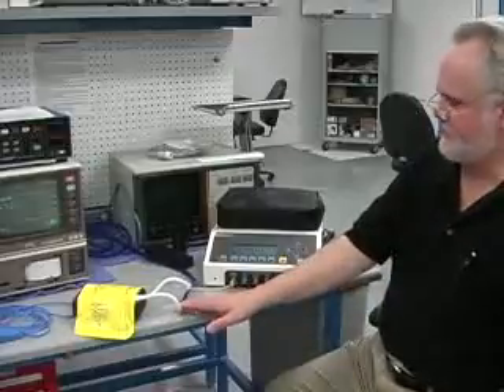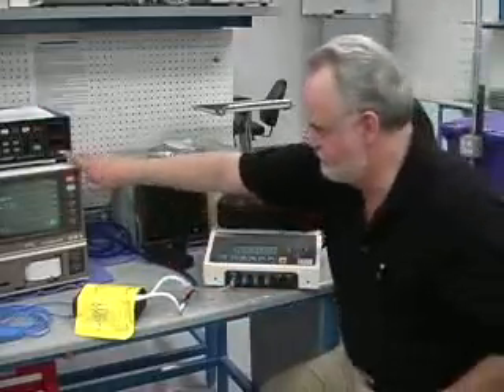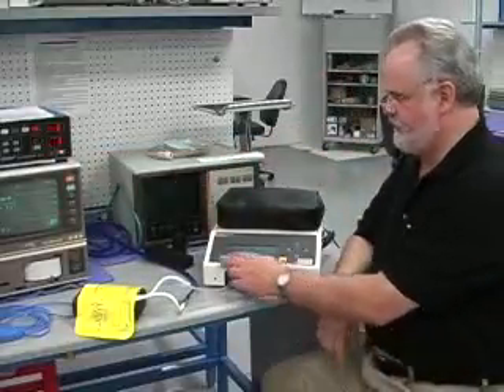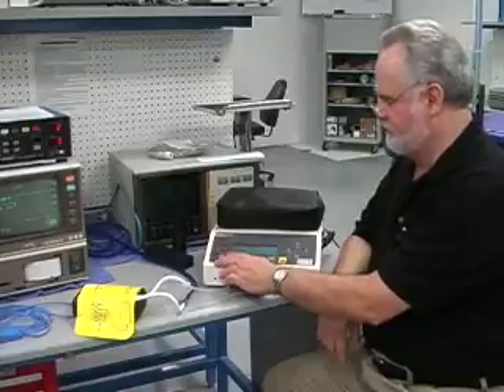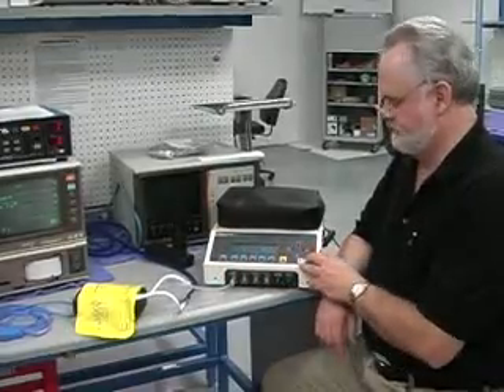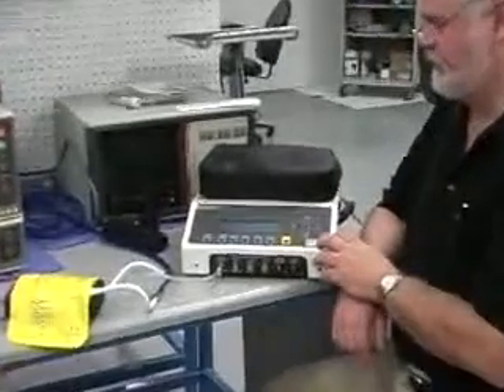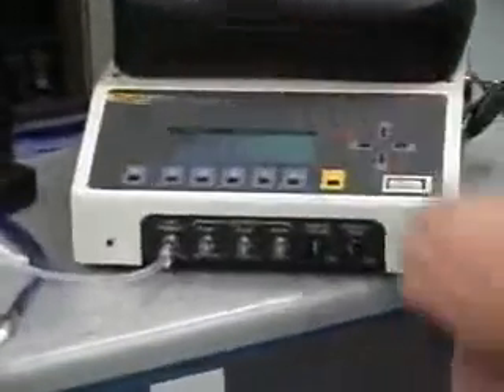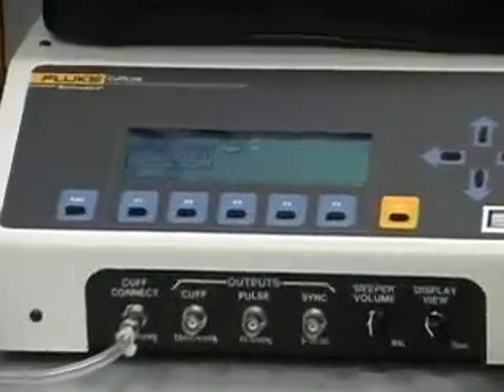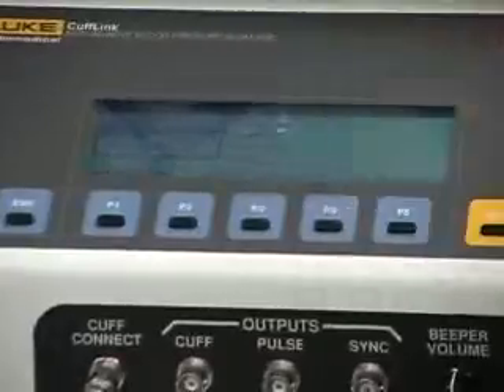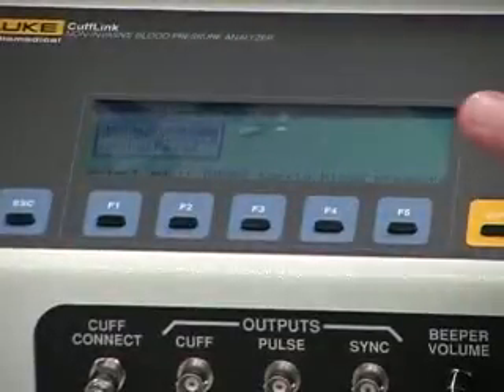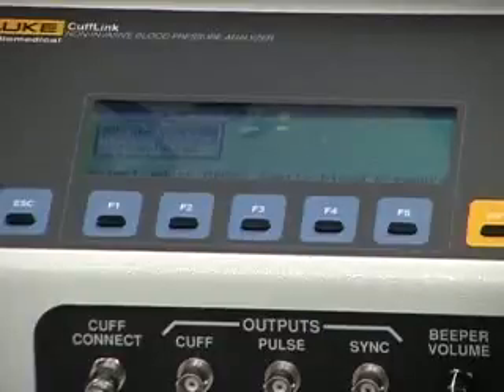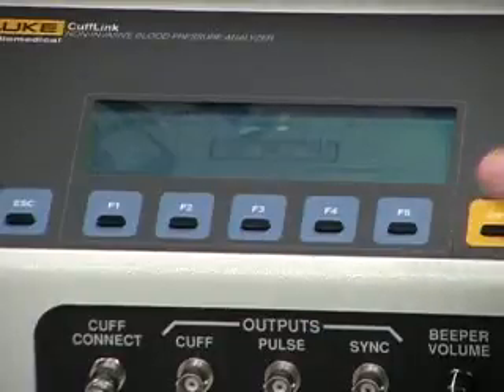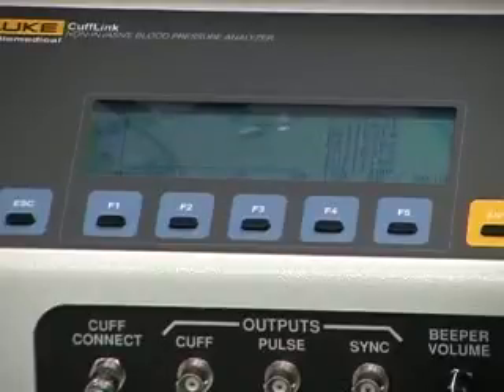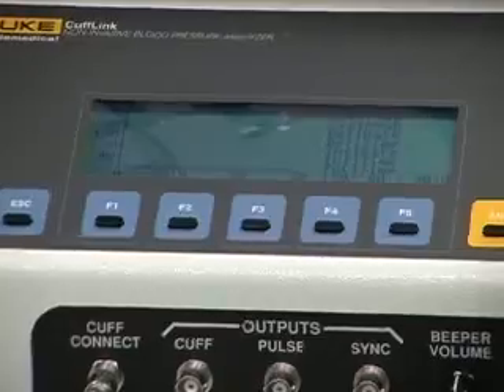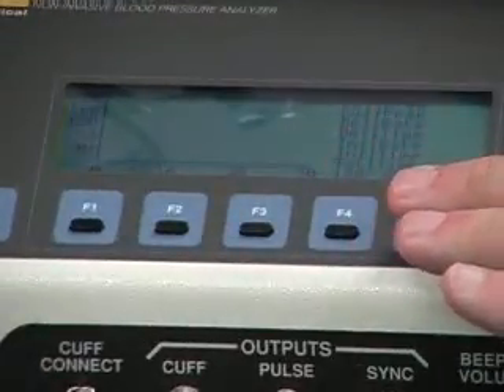So right now it's the same setup, everything's as we had before. Have the analyzer turned on, and just go back up to the main menu of the Cufflink. And again, it automatically defaults to the dynamic simulation, and as we call it, the Atoms family. And with that, after it goes through its little power-up routine, I said just hit enter twice, and that automatically gets you to a 120/80 dynamic blood pressure. And now, again, we're ready to go for 120/80.